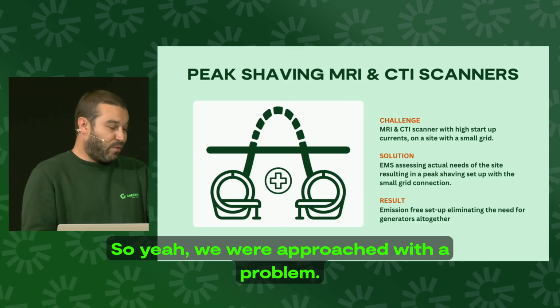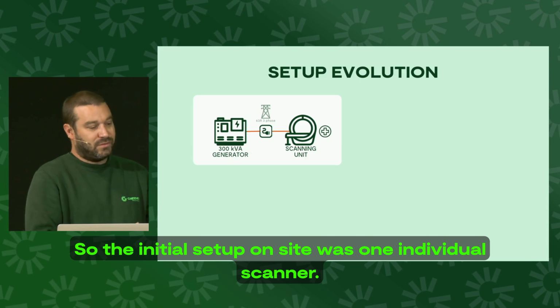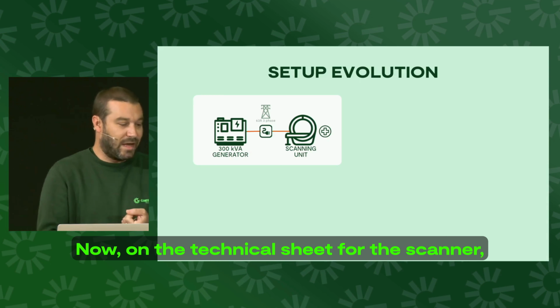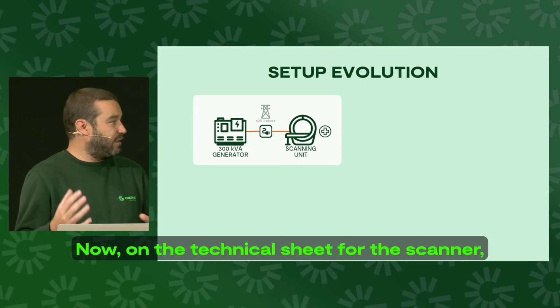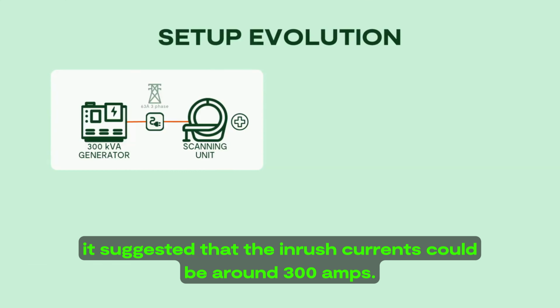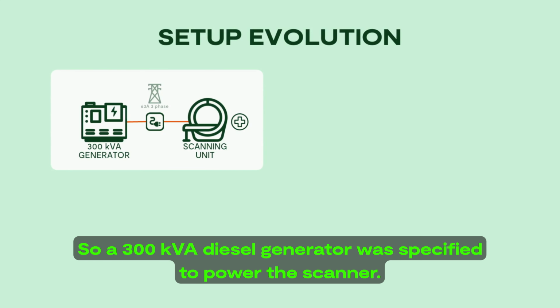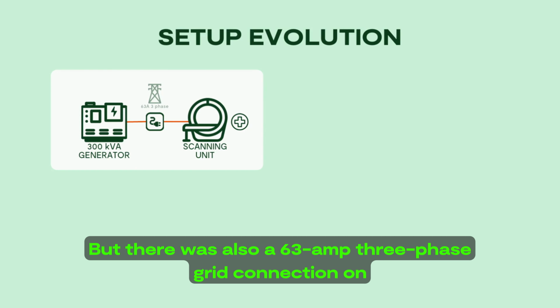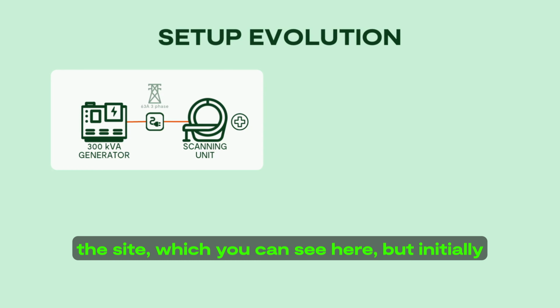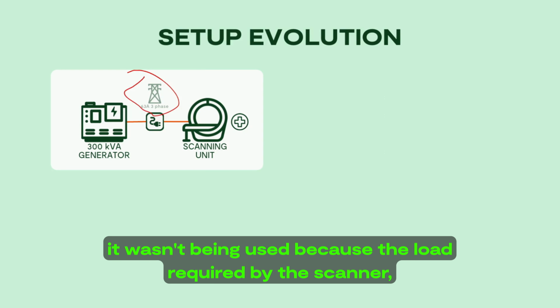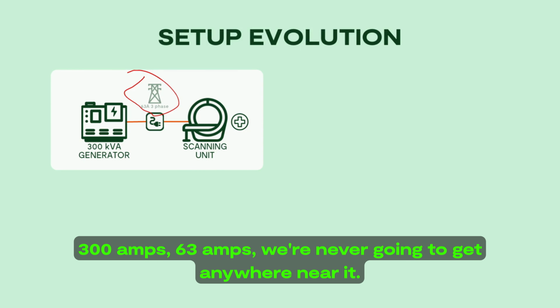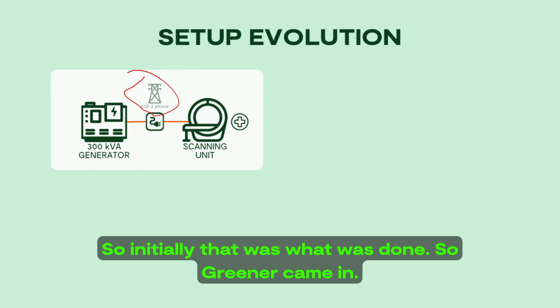So yeah, we were approached with a problem. The initial setup on site was one individual scanner. Now on the technical sheet for the scanner, it suggested that the inrush currents could be around 300 amps. So a 300 kVA diesel generator was specified to power the scanner. But there was also a 63 amp three-phase grid connection on the site, which you can see here. But initially that wasn't being used because the load required by the scanner, 300 amps, 63 amps, we're never going to get anywhere near it. So initially that was what was done.